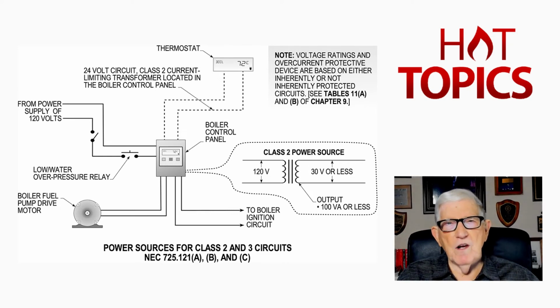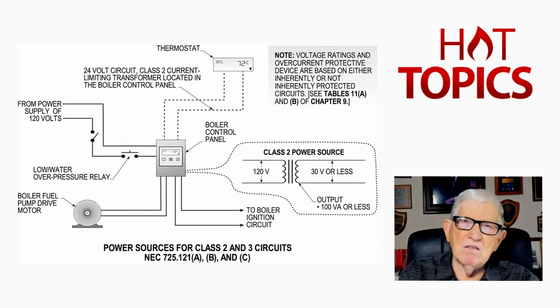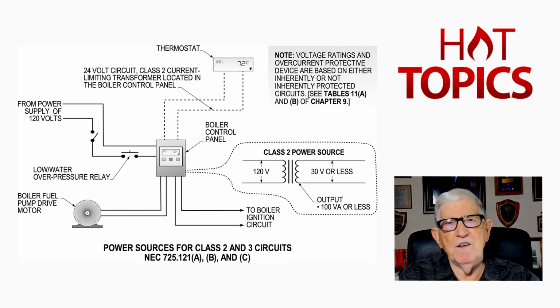Now, folks, there you have why it's very important that 110.4(C), as in car, and 70E requires low voltage systems to be evaluated before you work on them. But a Class 2, they don't tell you that. But for Class 1 and 3, yes, you would need to evaluate those circuits because they might be a shock hazard. Most designers say, well, your skin. That's why they start with that 50 volt rule.